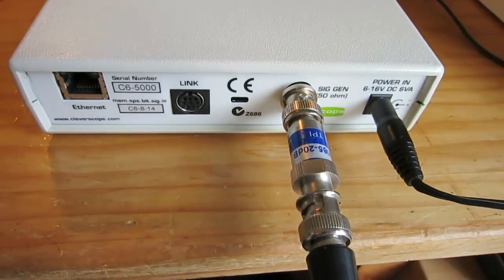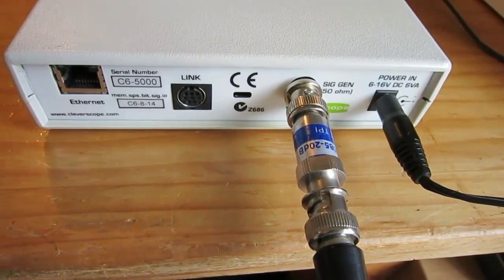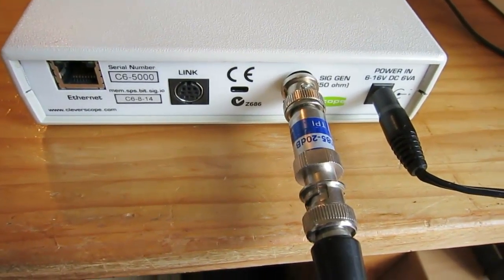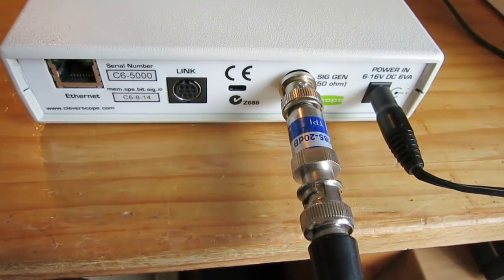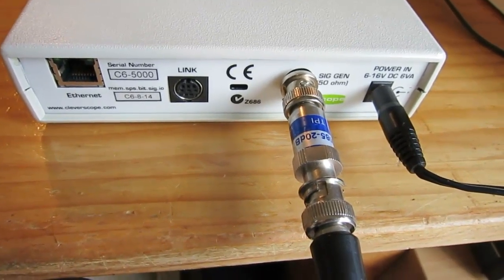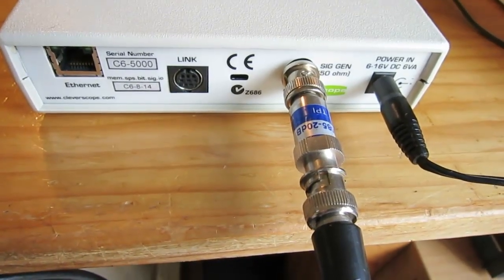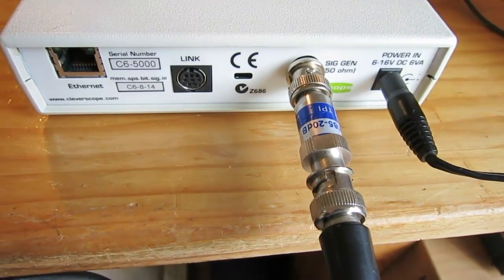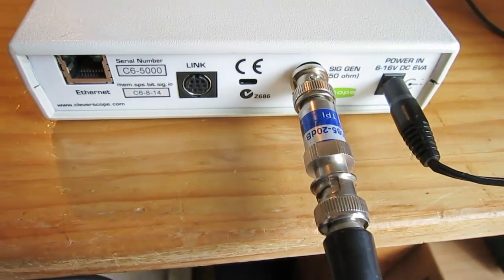The signal generator is connected to the isolating transformer using a 20 dB attenuator. This means that the preset 0.5 volts peak to peak coming out of the signal generator is converted to 50 millivolts peak to peak into the transformer.